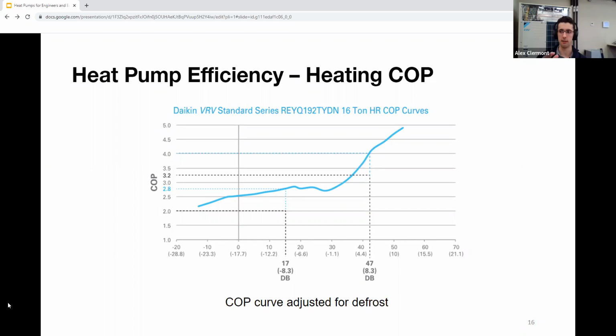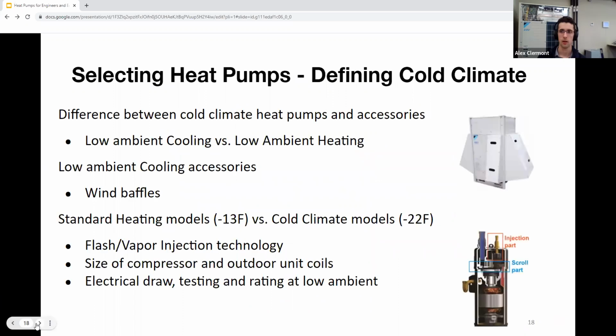You see this bit of a dip right around 30, and we'll talk about that in a little bit. It actually is caused by defrost of these air source machines. And we'll get into that in a little bit. But the COP being 2.8 at 17, and then as it goes to 0, it's about 2.5 there on the graph. So something I just want to mention really quickly is that this technology of heat pumps has improved tremendously over the past 2 decades. And just a reminder that gone are the days of heat pump operation only down to 30 degrees. Nowadays, with inverter-based cold climate heat pumps, we have heating data down to -13 and -22 as well.